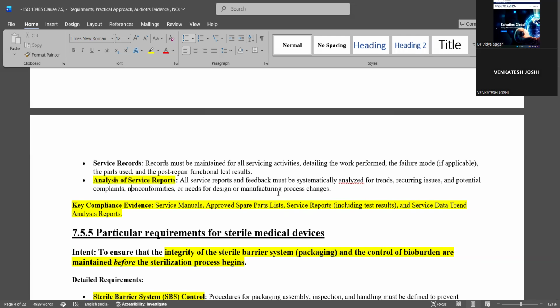You should analyze the trends, like in medical devices, which spare parts are getting replaced more, which parts are getting more service, where you need more servicing, and which equipment is getting wear and tear very quickly. You should know the trend analysis in that machine, what is happening with it, the health of the machine, how to take care of it, how many times you are doing maintenance.